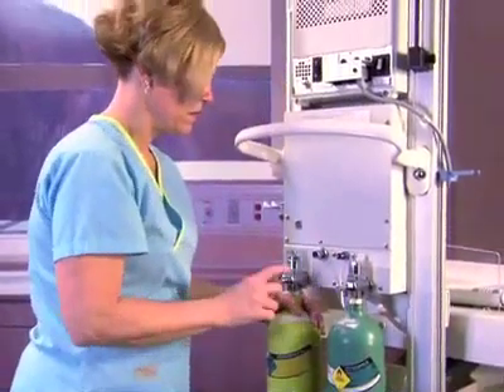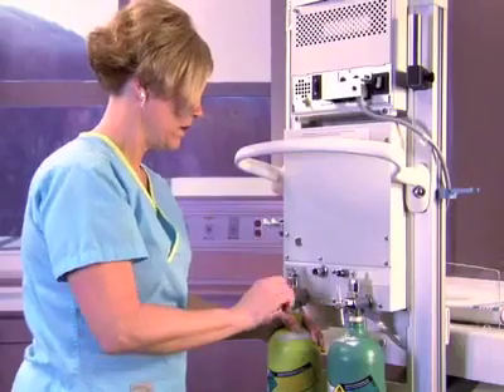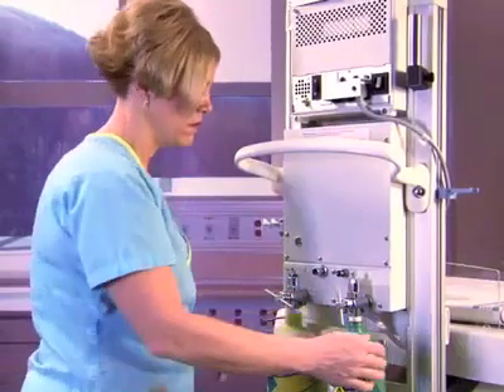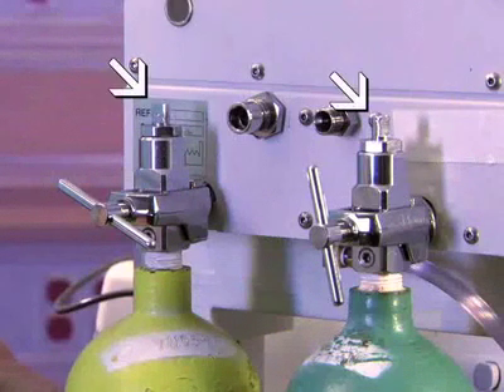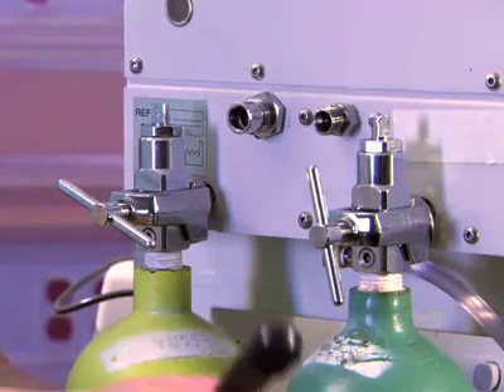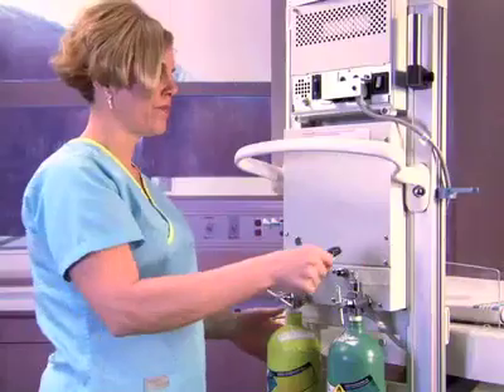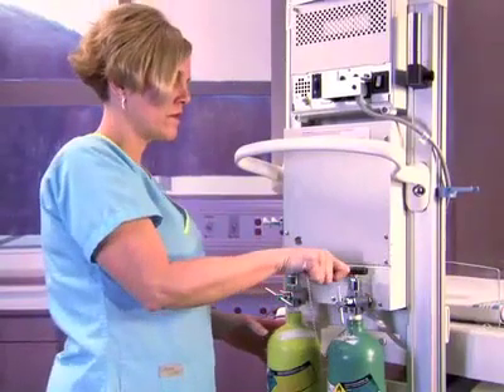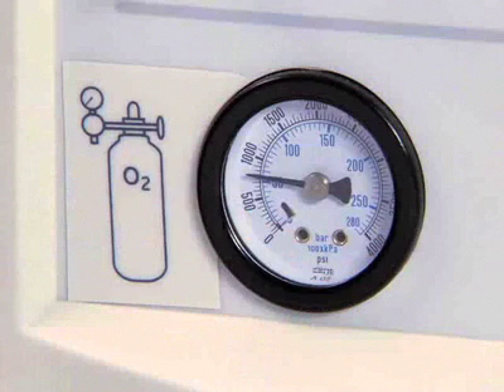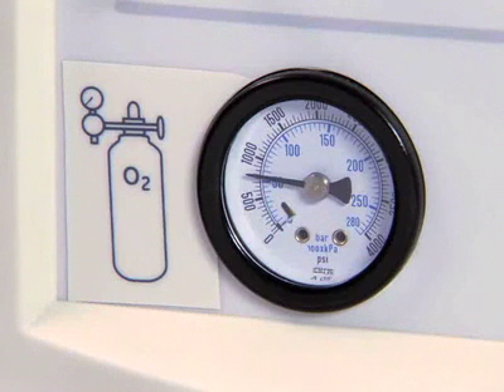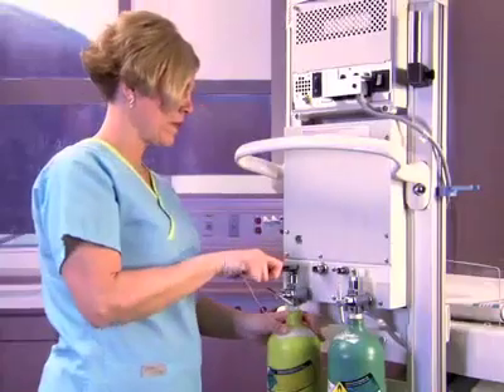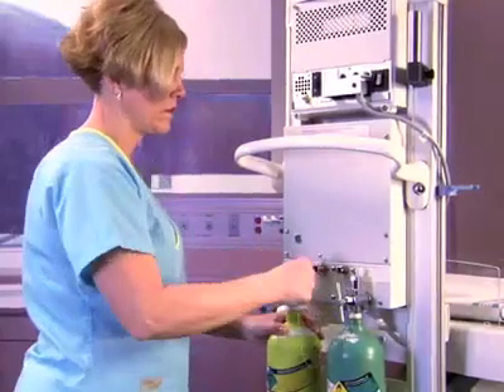The integrated high-pressure yokes are only available when you purchase the integrated blender option. Open tank valves slowly to avoid damaging the regulators. Use the tank wrench to slowly turn the valve counterclockwise and verify that the tank contains an adequate supply of gas by examining pressure on the gauge on the front panel of the resuscitation system. Repeat the process for the second tank.